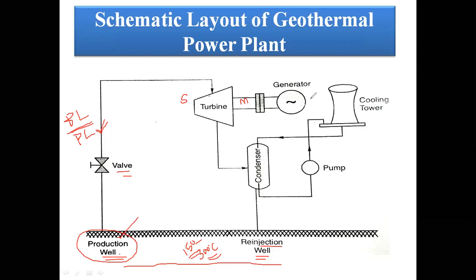Further, this mechanical energy converts into electric energy with the help of an alternator or AC generator. Actually, here the power is generated at 3.3 kV, 6.6 kV or 11 kV. Based upon the distance or the line length, we boost, or step up, the voltage with the help of a step up transformer.